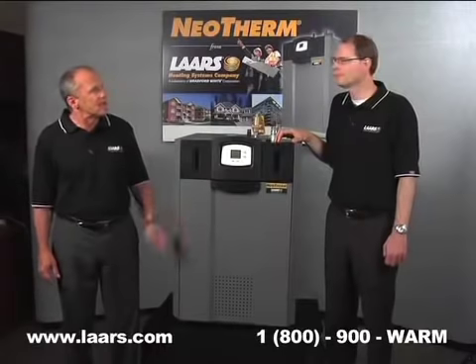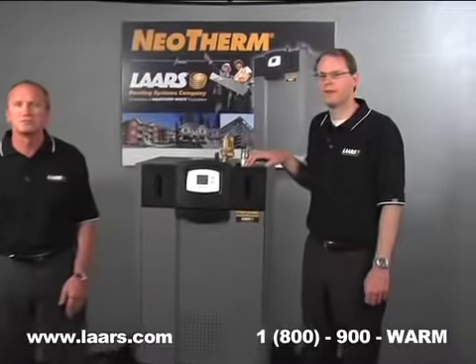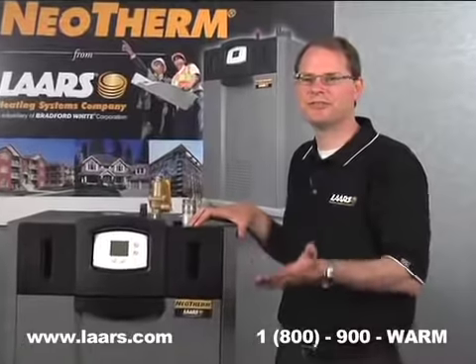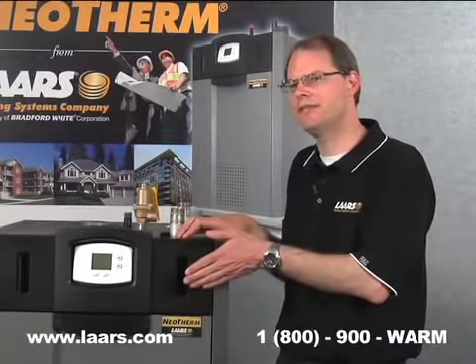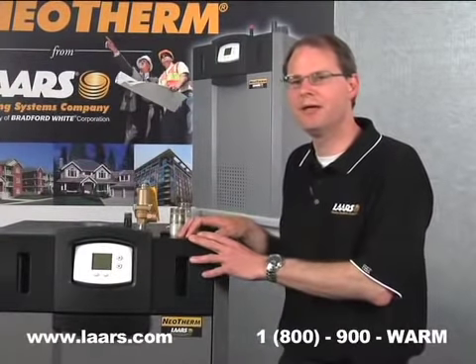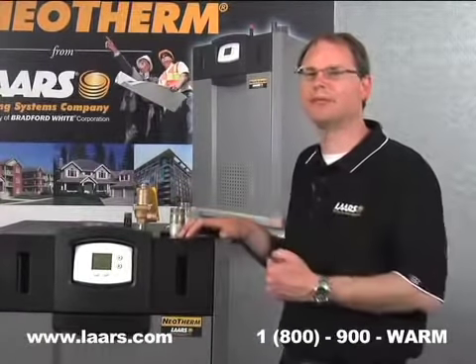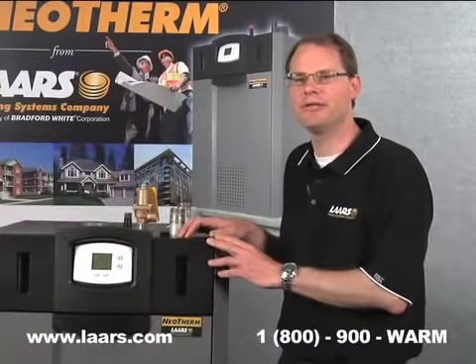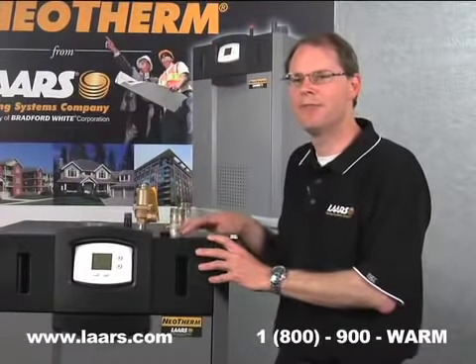So Tom, you want to wrap up on the commercial side, because this is not only a residential but a commercial product as well. Right, and for the commercial contractors out there, as John mentioned, the residential sizes start at 80,000 BTU input and go up to 210,000 BTU input. The commercial sizes start at 285,000 BTU input up to 850,000. And when you are able to lead lag up to 8 commercial boilers together, you get just under 7 million BTU input controlled properly to maximize your condensing efficiency with the NeoTherm product line.